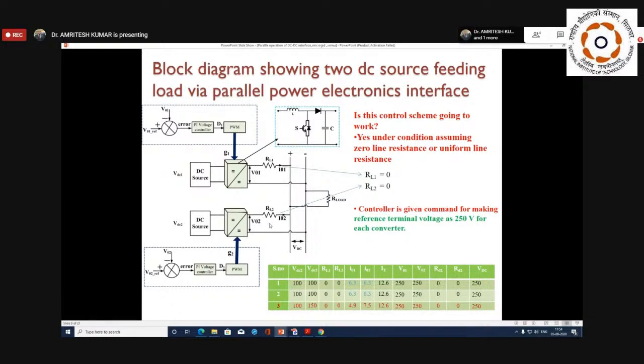It is simple, like in a power system, the PCC voltage, or you're talking about the grid voltage, is going to be maintained by the grid. And if a DC source wants to inject, it will inject as a current source. It will never try to perturb the voltage. It will just respect the grid voltage. Similarly here, if you have two sources and one source is powerful enough, then the other has to accept that. So that is happening here.